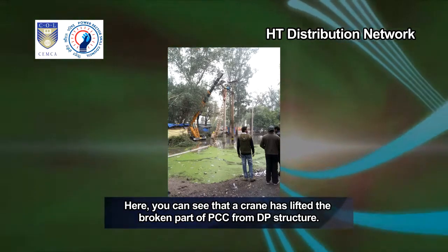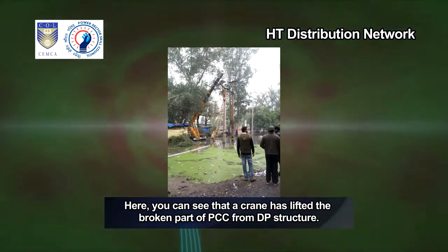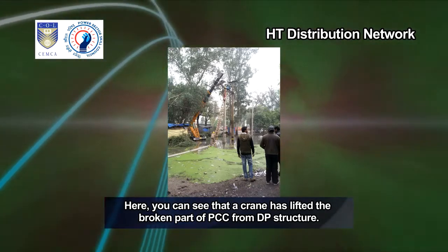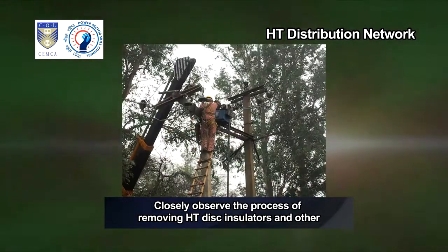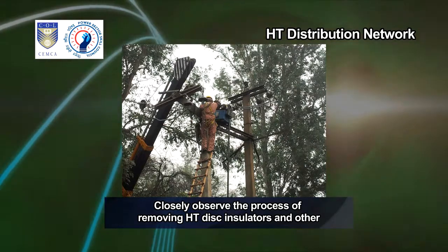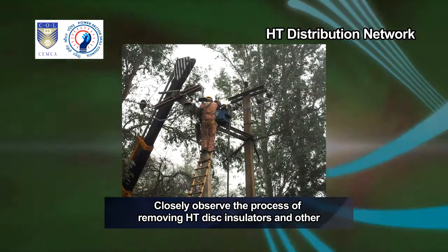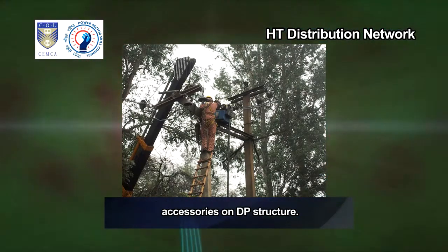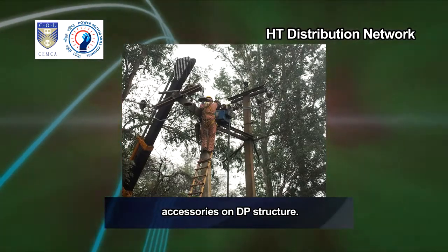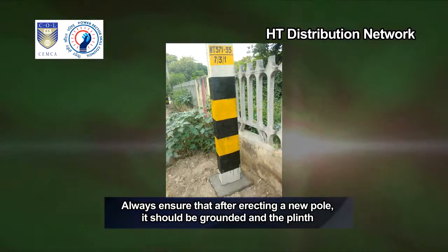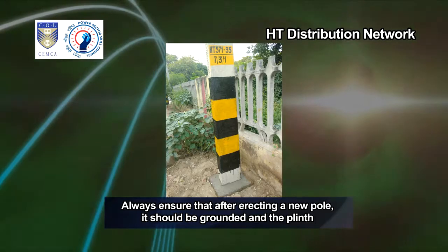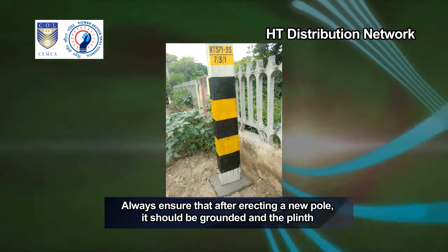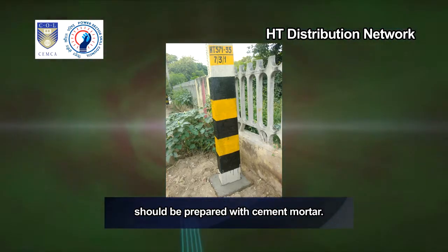Here, you can see that a crane has lifted the broken part of the PCC from the DP structure. Closely observe the process of removing HT disc insulators and other accessories on the DP structure. Always ensure that after erecting a new pole, it should be grounded and the plinth should be prepared with cement mortar.